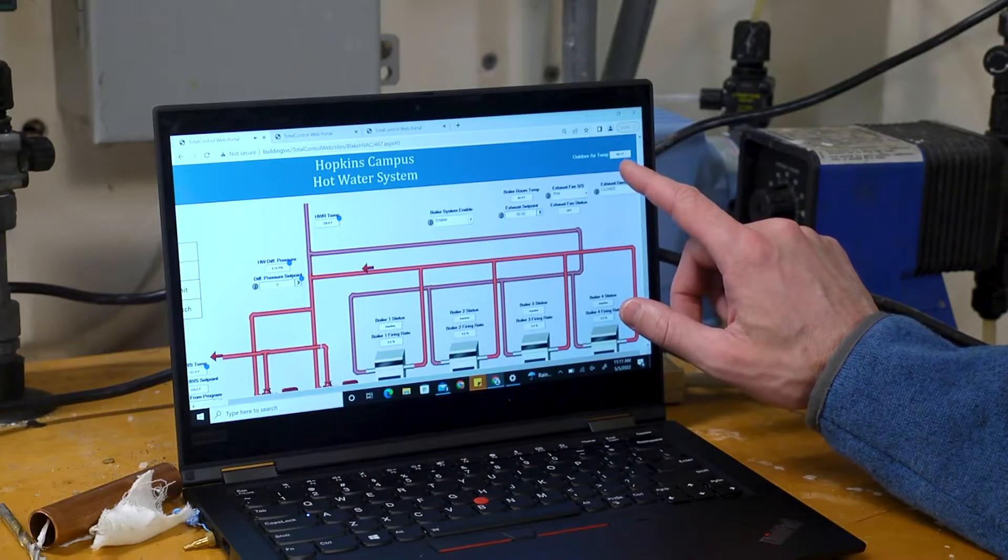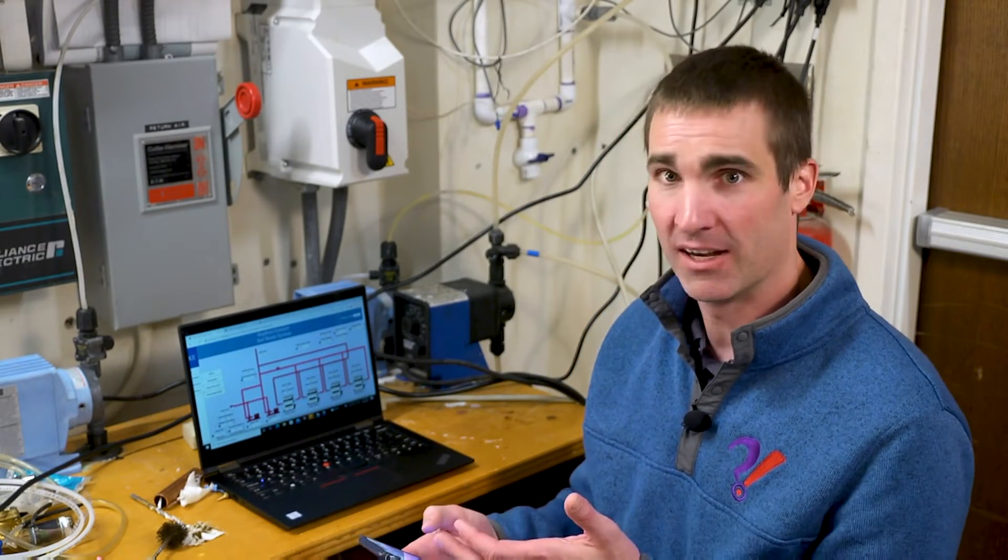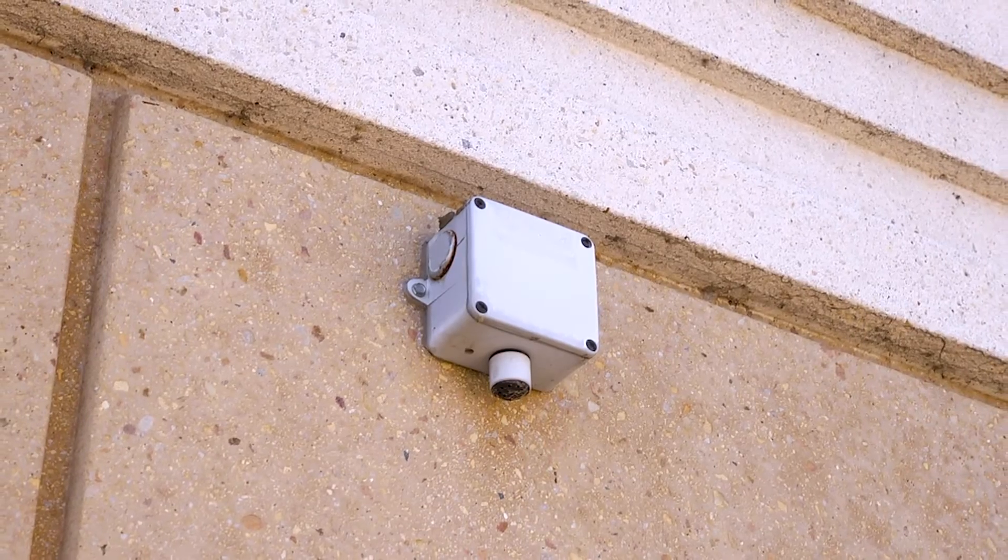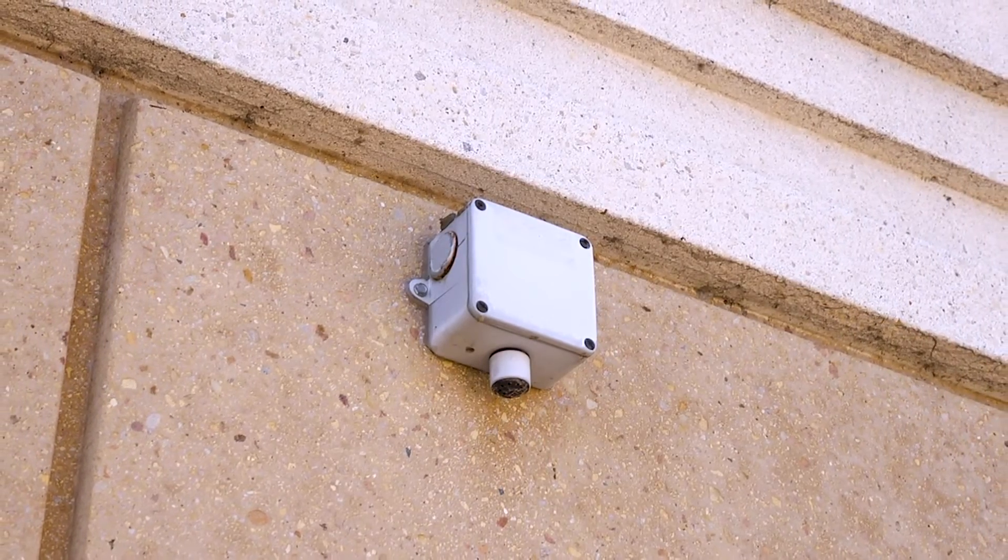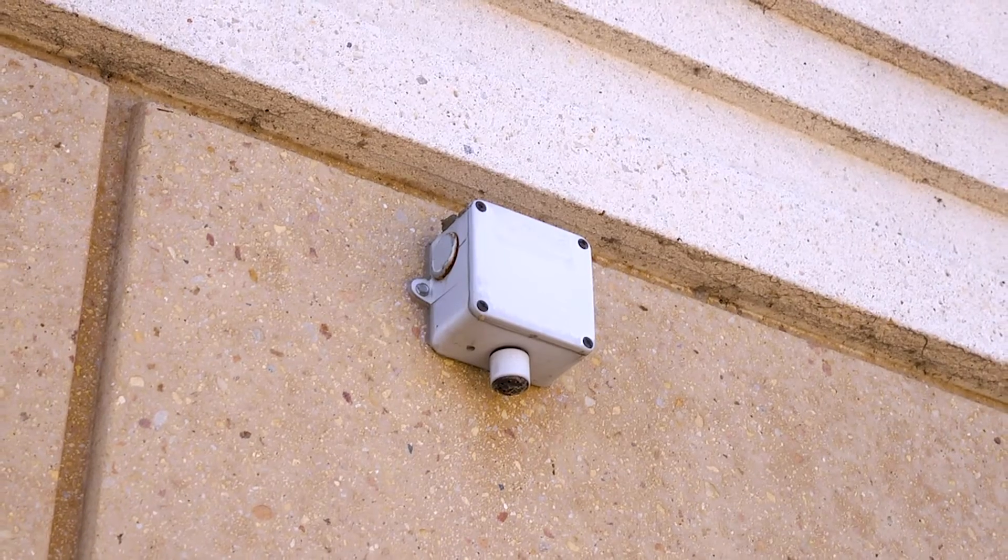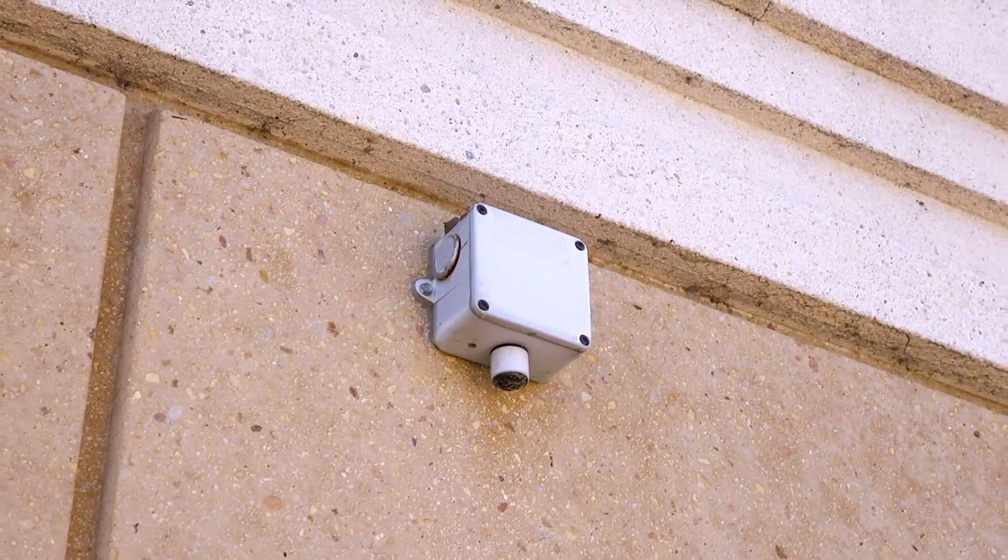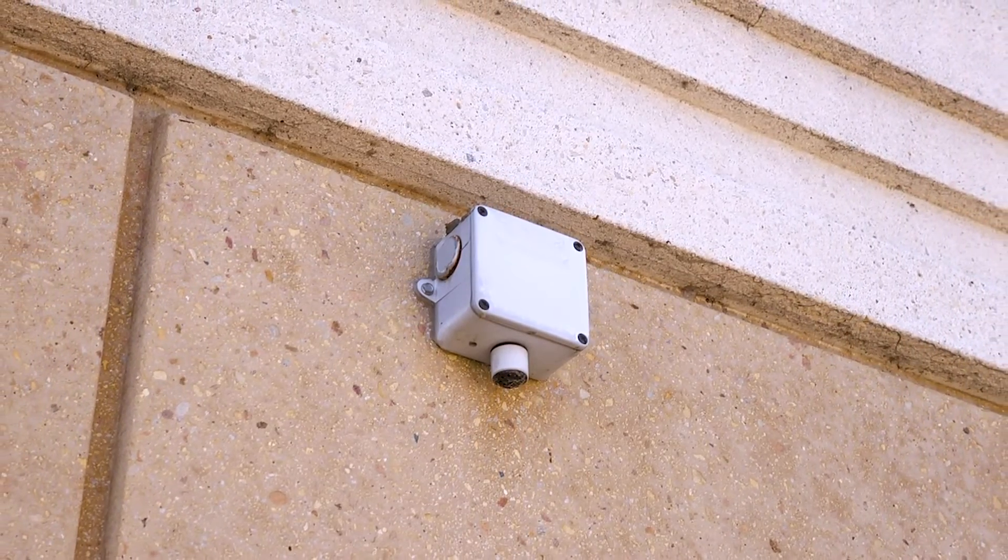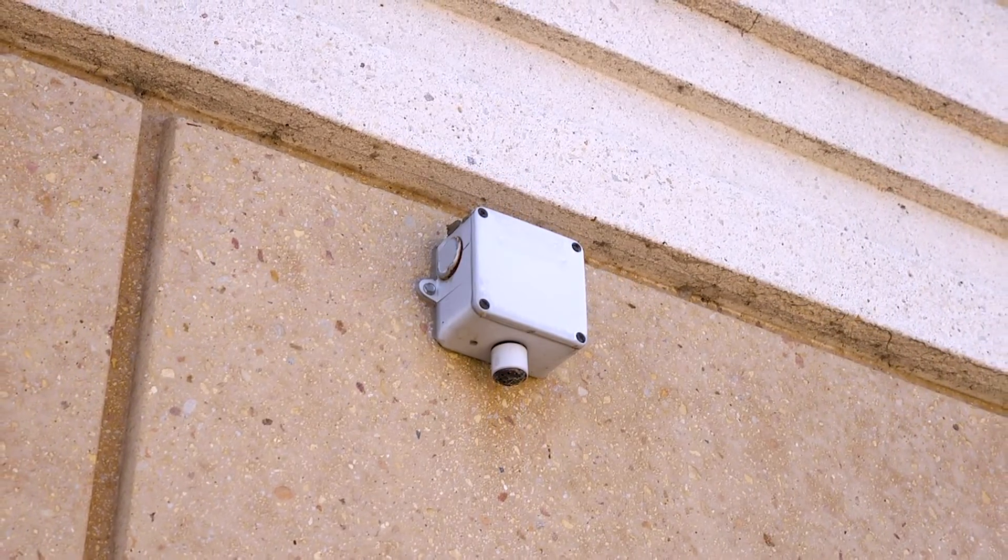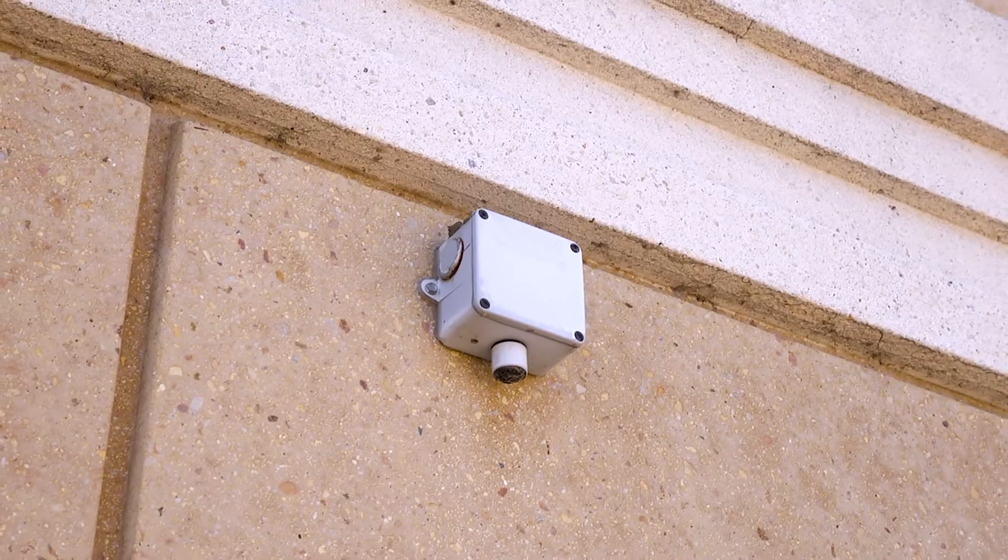I could do a sanity check on that outdoor air temperature sensor just by pulling up my phone, pulling up the weather app and comparing my reading on the weather app to the local reading here. If it deviates greatly, maybe the sensor location is not appropriate and it's getting too much sun. Or maybe the sensor has fallen out of calibration and needs to be either calibrated or replaced.